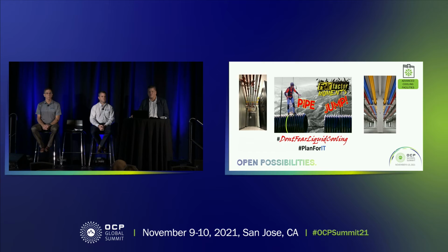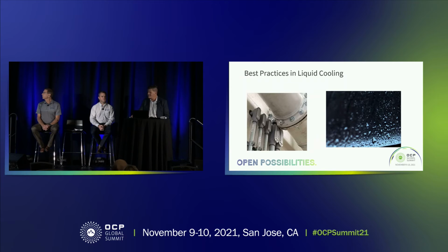I'm surprised my two co-speakers with some pictures they may have seen recently, but didn't expect I was going to put up here. Oh. So you want to talk about how these might apply to why you'd have a fear of liquids in your data center. There's a slight chance in that first one that the integrity of the gasket might be compromised, or maybe the clamping force of that flange. But yeah, despite everybody's best intentions, through design, through manufacturing, through product development, so on and so forth, everything comes down to execution in the field.